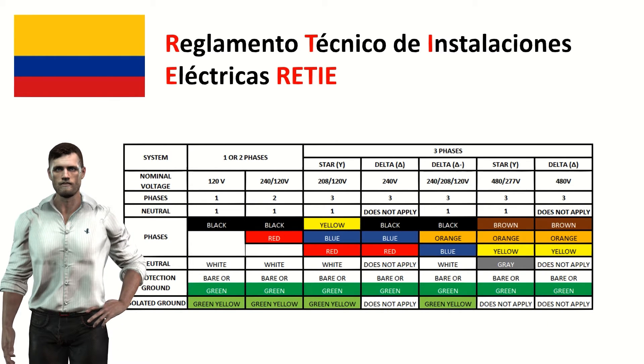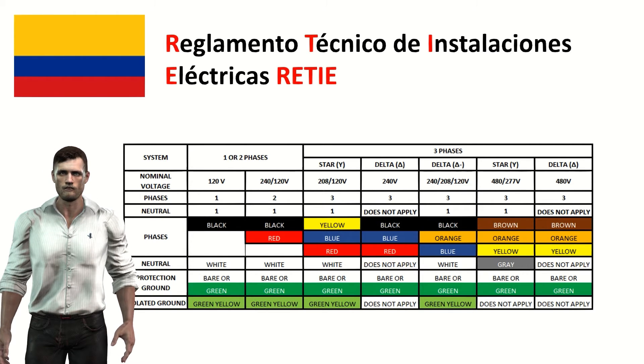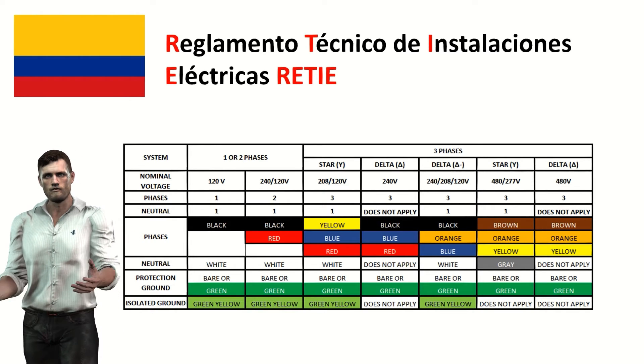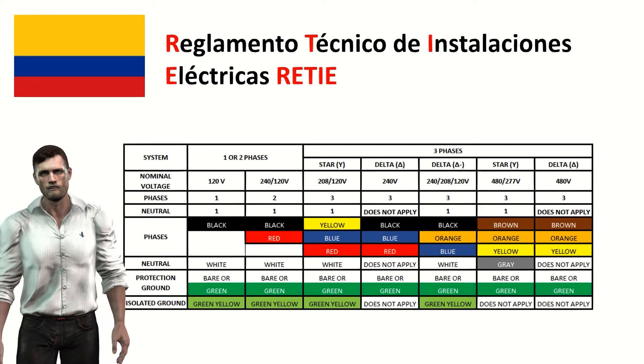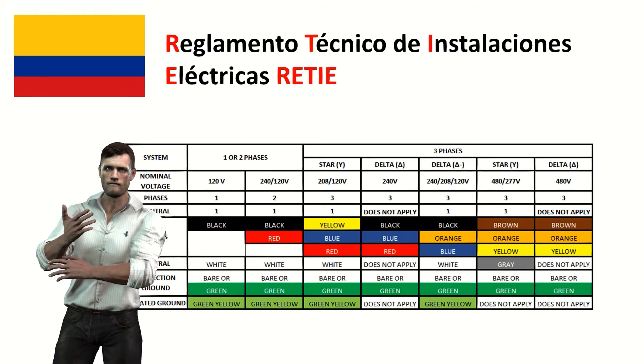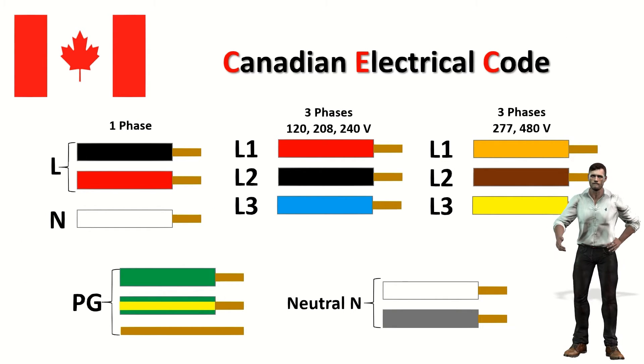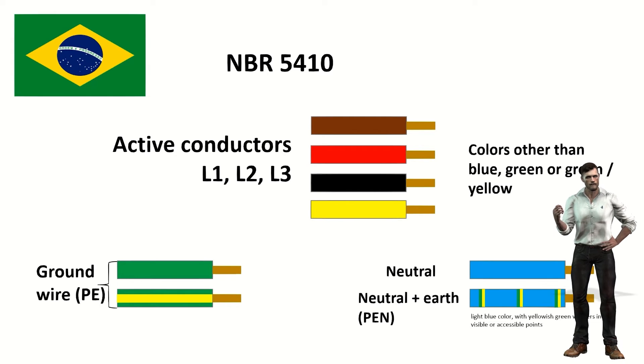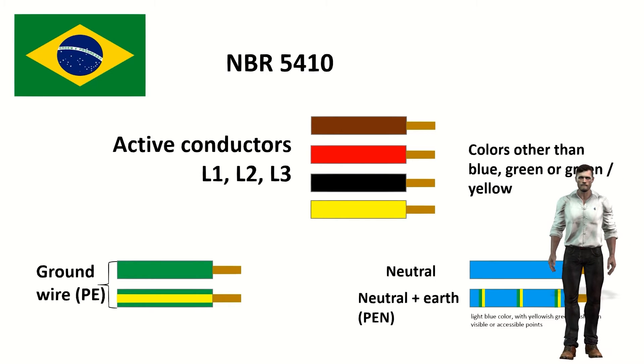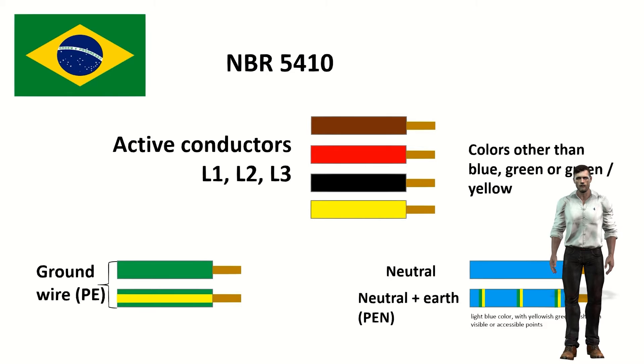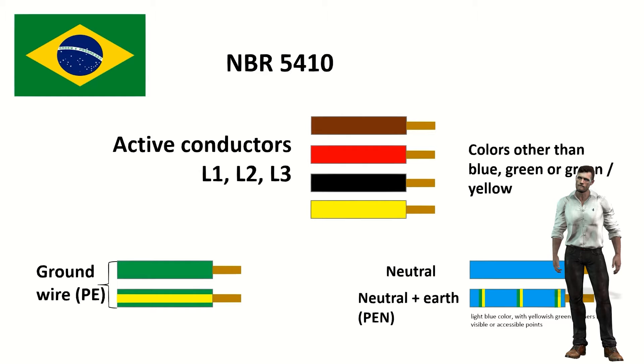In Colombia, the color code is established by the Reglamento Técnico de Instalaciones Eléctricas, which distinguishes the color of the phases based on their voltage, whether they are single-phase or three-phase, and also depending on the type of installation, that is delta or triangle. For the protective earth the color green is used or the bare copper wire, and for isolated earths the color green-yellow is used. The table below shows the different color combinations. In Canada, the Canadian Electrical Code uses a coding very similar to that of the United States. In Brazil, the color code is regulated by the NBR 5410 standard, which defines blue for the neutral and green or yellow-green for the earth wire (PE). If the neutral is also distributed as a protection wire, called PEN, then it will be blue with green and yellow washers at visible points. Colors other than those already mentioned are allowed for active cables, for example brown, red, black, or yellow.